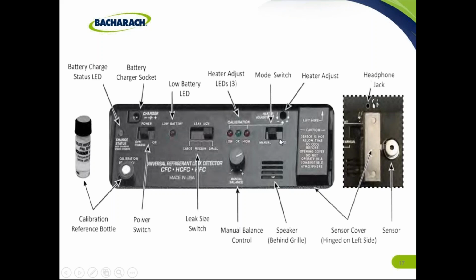If you put this in the auto mode, when you put the probe into gas and you start getting a faster tick and the light in the probe flashes faster, if you leave it there for several seconds, then it will automatically adjust to that. And it'll go back to several ticks per second, and then you can go further and look for the leak. The manual mode is more sensitive, and you will find more leaks in the manual mode.